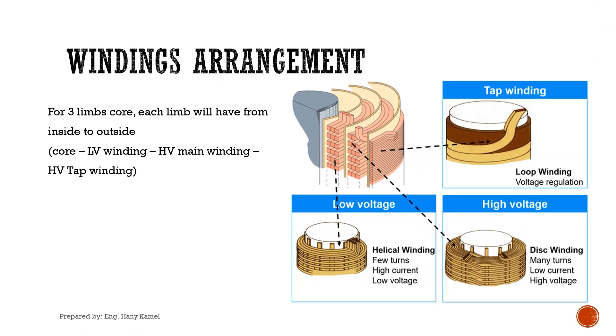Windings arrangement. For a three-phase transformer, each phase will be on a limb or leg. Each limb will have, from inside to outside: core, then low voltage winding, then high voltage winding, then high voltage tap winding, also called regulating winding, as we can see in the picture.